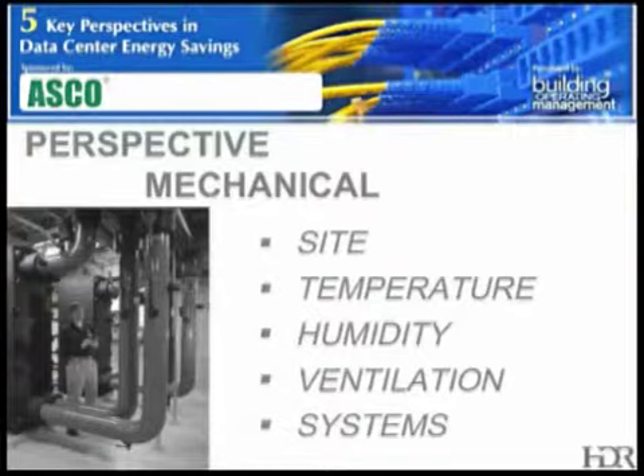operated to their benefit. One of the things that's really happened as a result of applying the ASHRAE criteria are a few things. Of course, the expanded use of the economizer cycles, which was really one of the original intentions that ASHRAE had for modifying the documents. The other thing is it permits the chilled water temperatures, if you're going with some kind of a CRAC or air handling unit approach, to be elevated, and that could really improve chiller plant efficiencies if the chiller plant is capable of running at temperatures somewhere in the 50s as opposed to temperatures in the mid-40s.